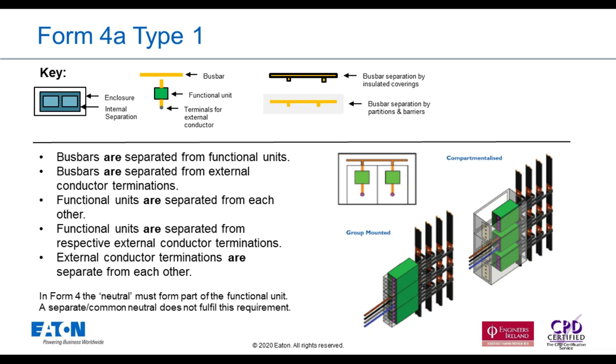So you've got Form 4A Type 1. The main difference when we move away from Form 3 is that in Form 4, the neutral must form part of the functional device. It can't be a common neutral. The neutral needs to come into either a 4-pole breaker or into a compartment where the functional device is sitting. And also, the external cable terminals need to be separated from one another. So in this example, you can see that you've got a group mounted and a compartmentalized. Group mounted is not very common when you come to Form 4, but it can be done.